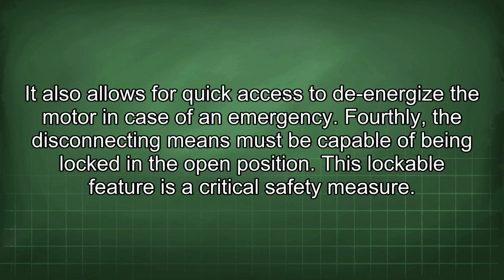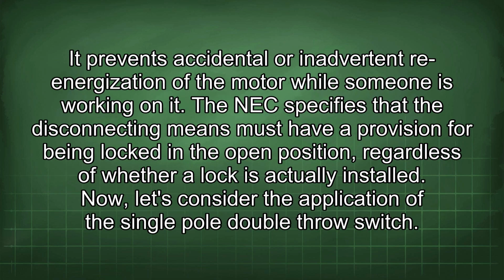Fourthly, the disconnecting means must be capable of being locked in the open position. This lockable feature is a critical safety measure. It prevents accidental or inadvertent re-energization of the motor while someone is working on it. The NEC specifies that the disconnecting means must have a provision for being locked in the open position, regardless of whether a lock is actually installed.